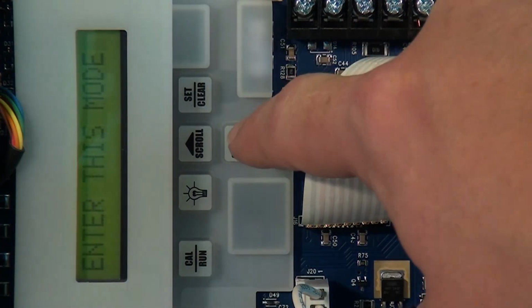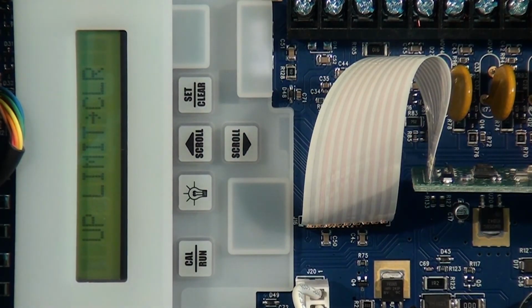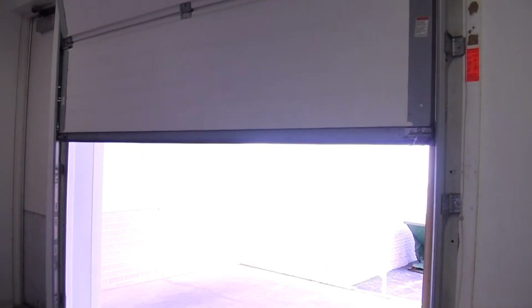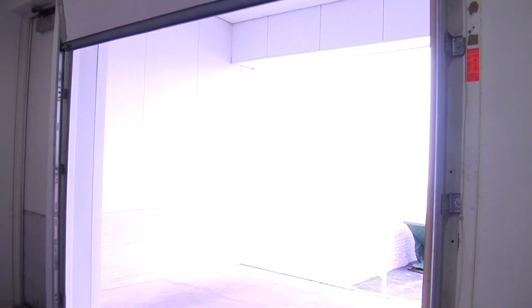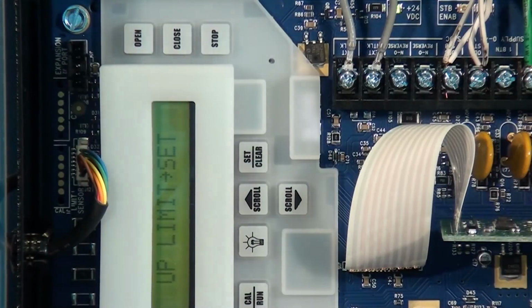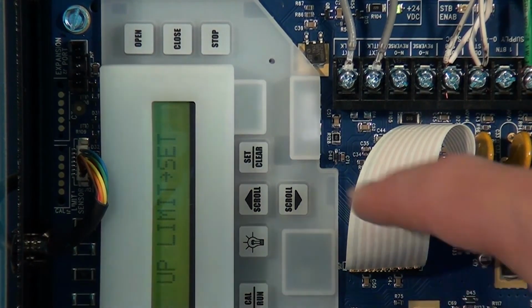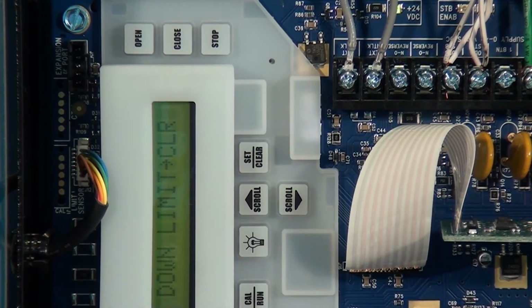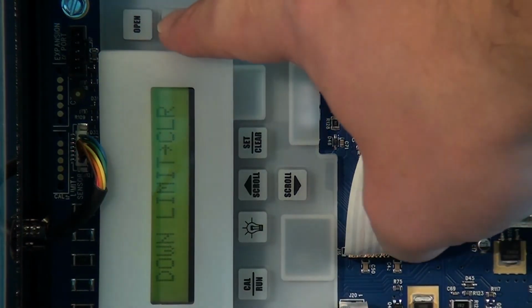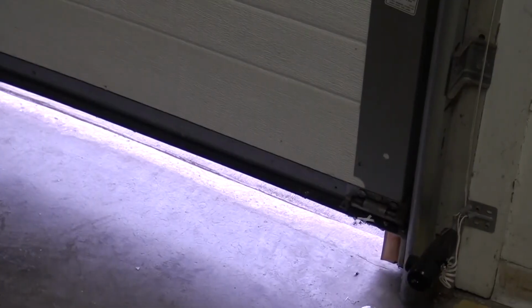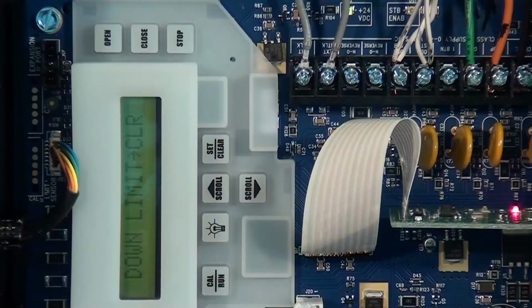Press the scroll down key until the display shows Up Limit Clear. Raise the door using the open key until you reach the desired height. Press the Set Clear key to lock in the up position setting. Now press the scroll down key until the display shows Down Limit Clear. Lower the door using the open and close keys until the door is 2 inches above the desired close position. Press the Set Clear key to lock in the down position setting. Please note, the recommended set point for the down limit is normally around 2 inches off the floor. This final distance will be covered by the limit overrun function to establish a more accurate seal.